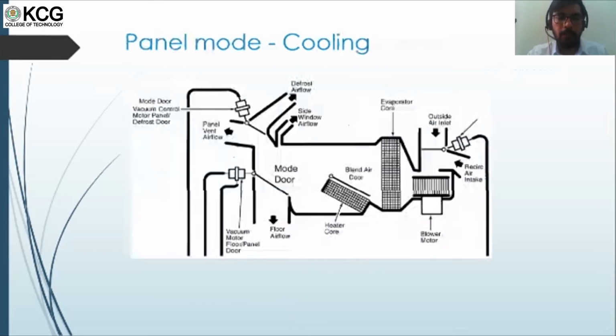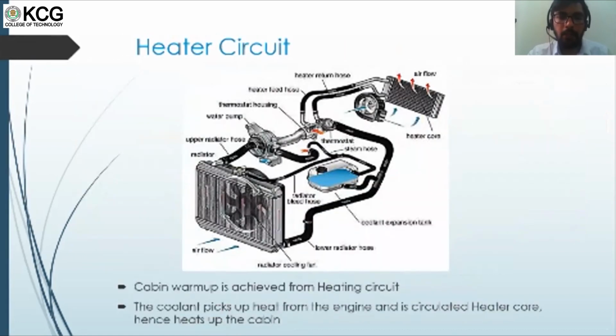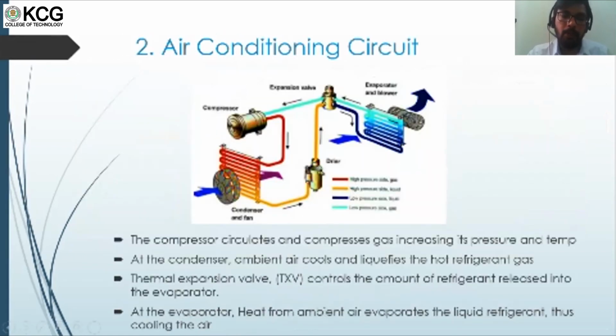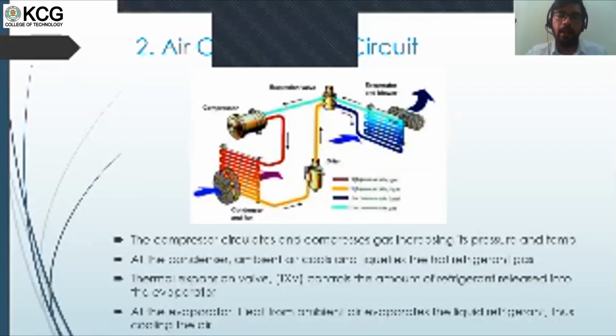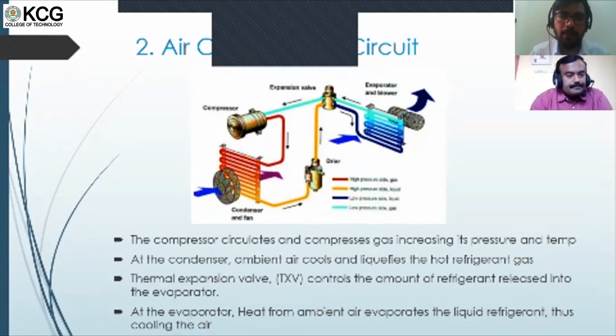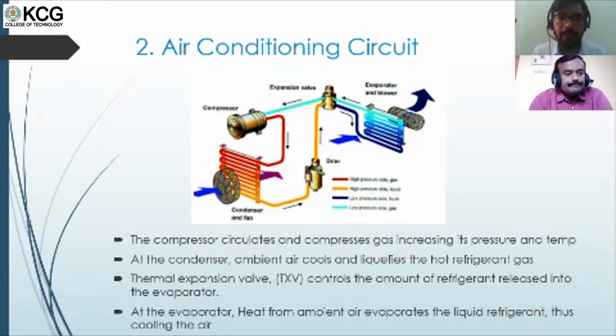During summer, your ambient temperature will go very high, so your condenser temperature may reach up to 90 to 100 degrees Celsius. At that point of time, your complete system will operate at maximum pressure. I would recommend that before summer itself, you get the maintenance done, all leaks, gas recharge if required, everything. During summer, if you have any problem, yes, but at least once a year or once in 6 months, you should get your AC system checked.